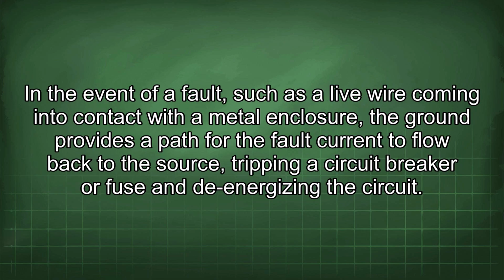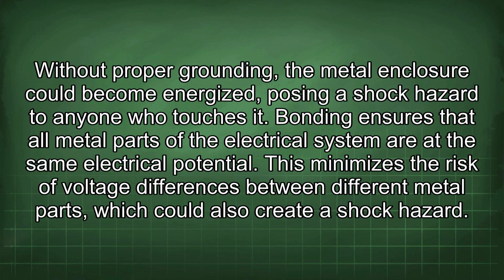In the event of a fault, such as a live wire coming into contact with a metal enclosure, the ground provides a path for the fault current to flow back to the source, tripping a circuit breaker or fuse and de-energizing the circuit. Without proper grounding, the metal enclosure could become energized, posing a shock hazard to anyone who touches it. Bonding ensures that all metal parts of the electrical system are at the same electrical potential. This minimizes the risk of voltage differences between different metal parts, which could also create a shock hazard.